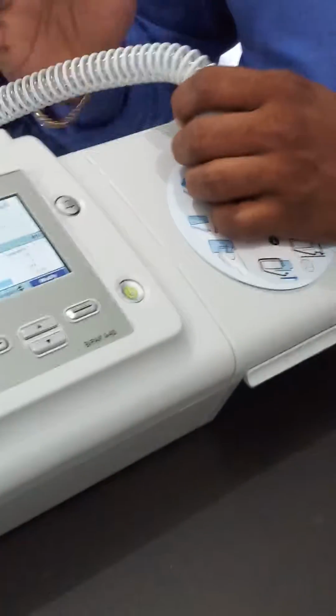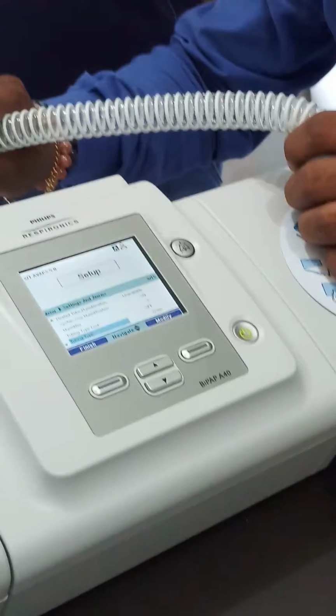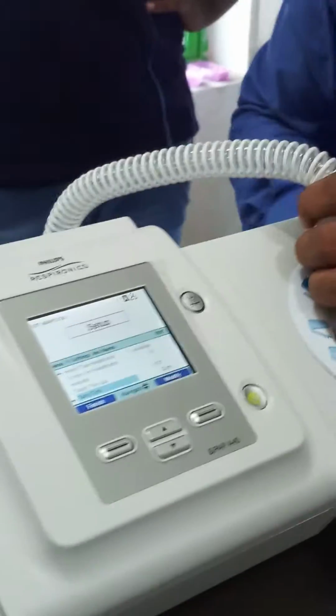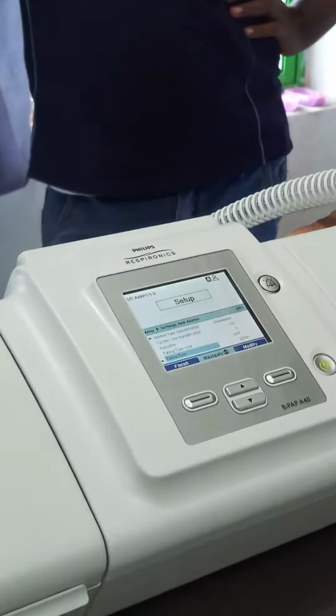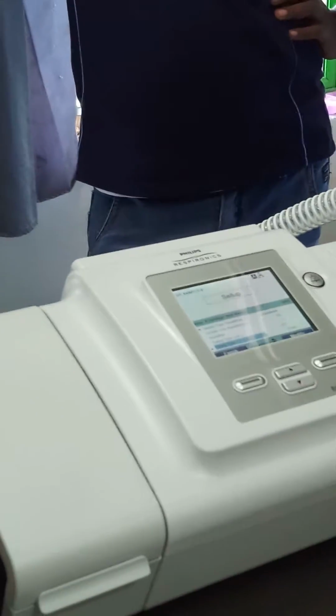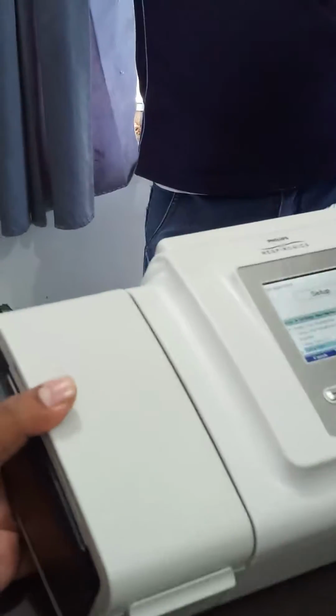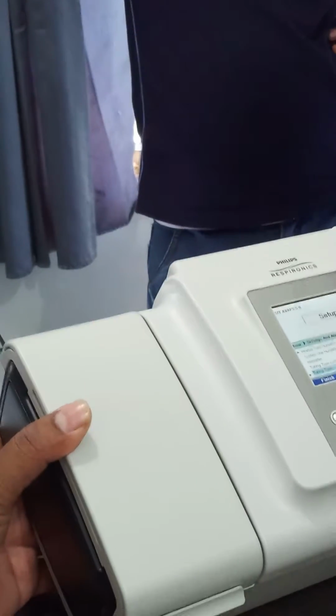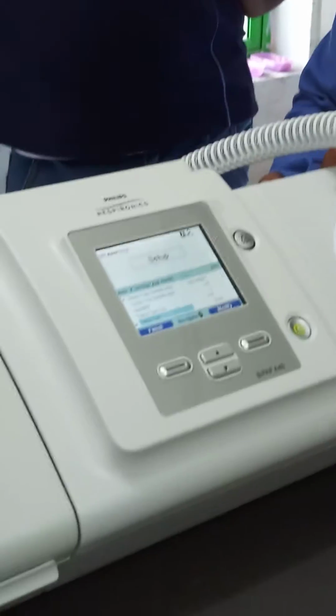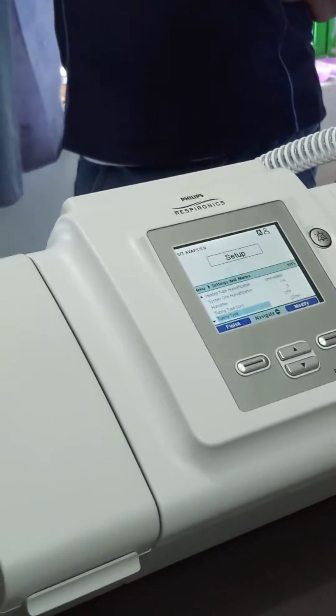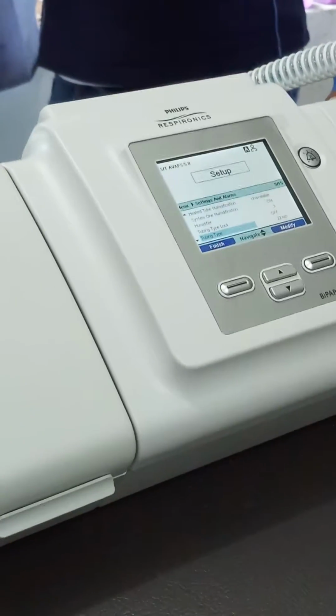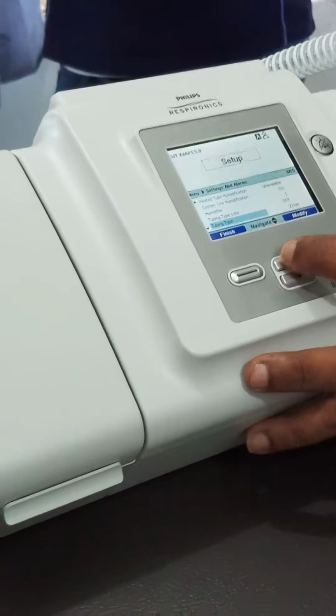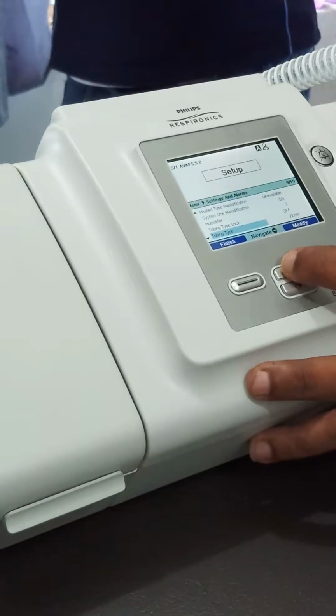You can't use it without the 15 tube. Because the dimension is changing, the pressure will be more, since the dimension is big, and it could cause damage. The thing is, we limit the peak of the pressure. For adults they can go to a maximum of 20 or 40, but for children that is too high. Sometimes it triggers and adjusts the peak. It can go maximum, yes.